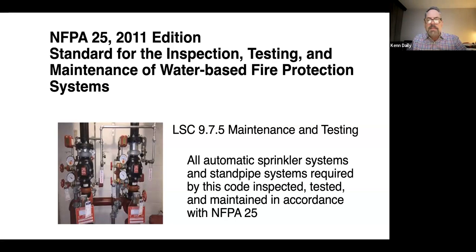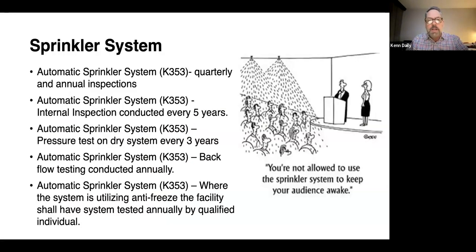And then most of that is going to be done by a contractor. You're required to maintain it, make sure it's not damaged, make sure it's maintained at 40 degrees. There is a requirement that we maintain our sprinkler systems at 40 degrees or higher at all times. And then we have to have an individual or vendor contract to come in and inspect, test, and maintain it according to the code. We have automatic sprinkler systems, quarterly and annual inspections. Again, every 90 days, you have your sprinkler company come in and do their thing. You would have the internal inspection every 5 years.